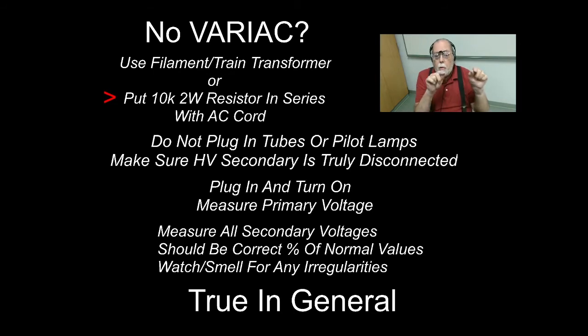Then you measure the voltage across the transformer primary. Then check the voltage on all the secondaries, and you want to see that they're the correct percent of their normal values. If you've got 10 volts across the transformer primary, you should have 10/120ths, or whatever that ratio is, of the voltage across all the secondaries.